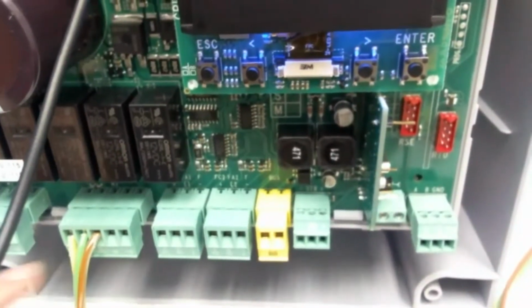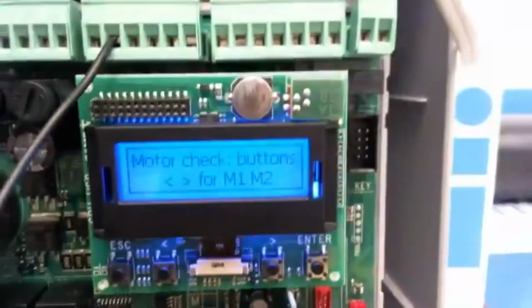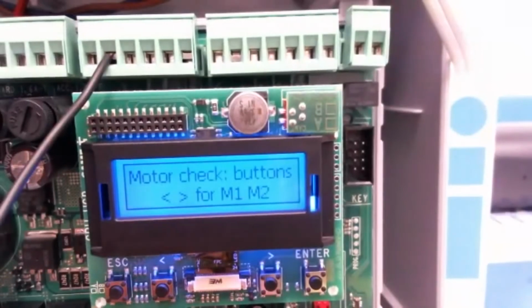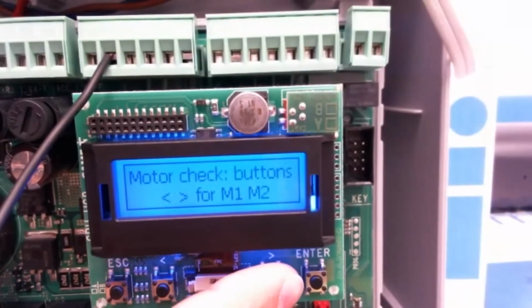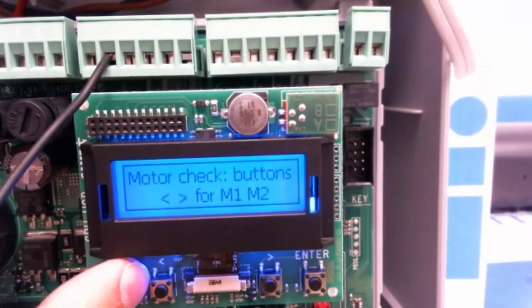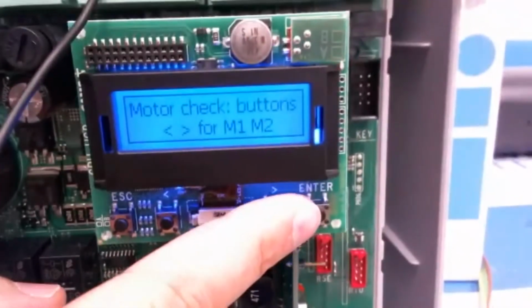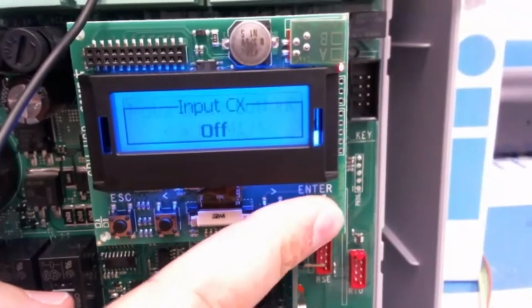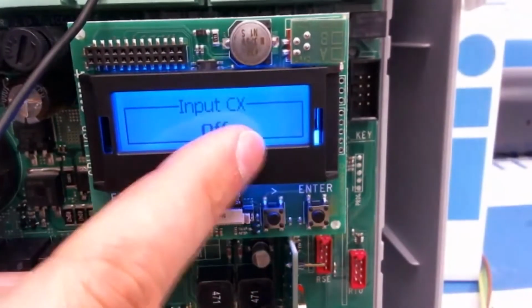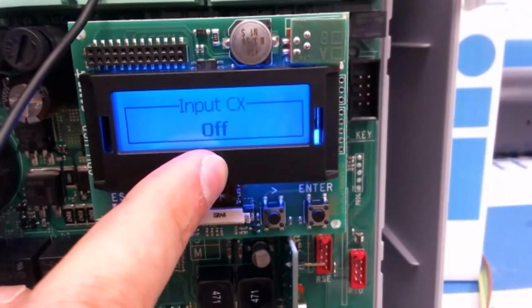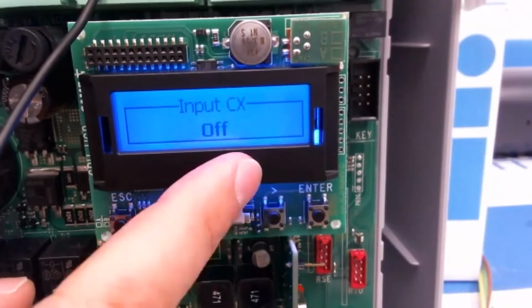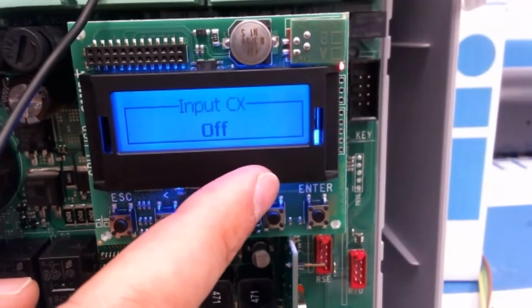In this case, you have to revert this one, these two, but it depends on the operator, so you have to see the instructions for the operator on how to revert the direction of opening. That's why it shows this as a step, because you have to check if the operator is connected correctly. Since right now it's opening correctly, I press enter. The next step is enable input, safety inputs, and like I told you, it has 4 inputs: CX, CY, CZ, and CK.